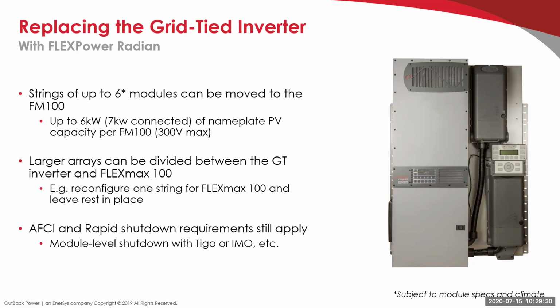But we'll talk a little bit more about the trade-offs between AC and DC coupling. I think in the long run, DC coupling, if you can go that route, especially on a new system, I would always recommend DC coupling for a new system. I would not design an AC coupled system from the get-go. You might think, oh, well, the grid-dependent inverter has better efficiencies. But where we have storage, you have to keep in mind you're going to lose 15% of that energy when you're charging the batteries. So all those gains that you think you're having kind of go away when you're charging batteries.